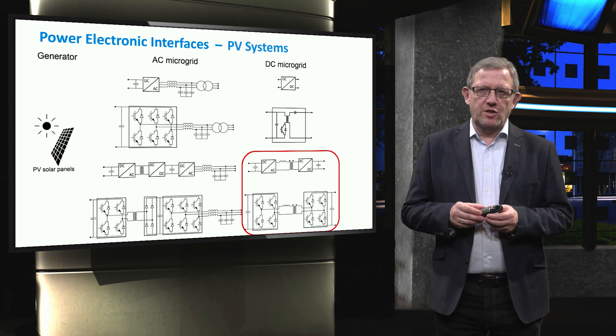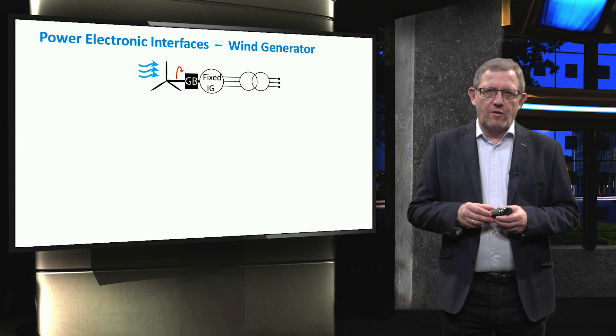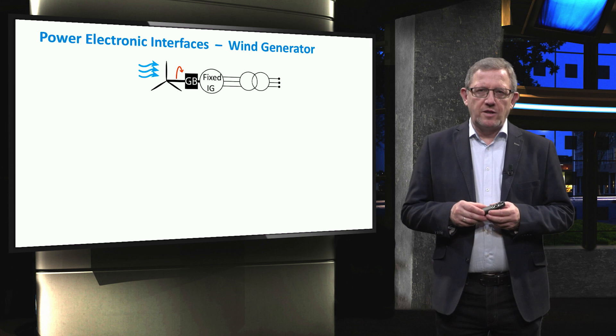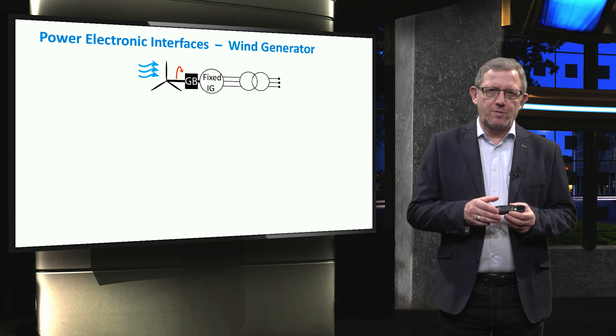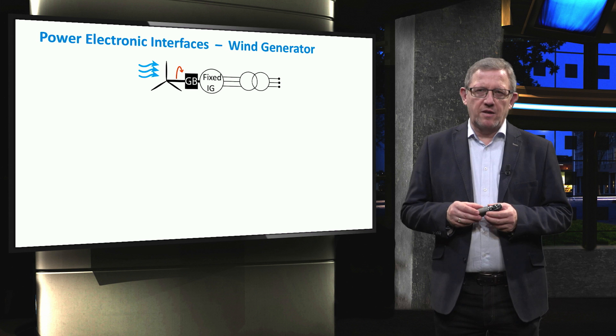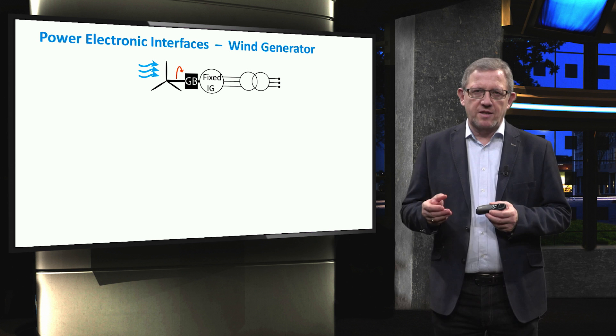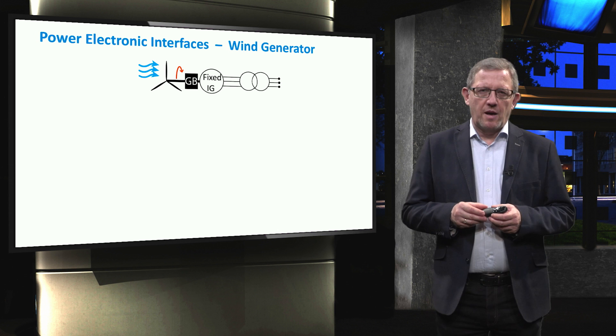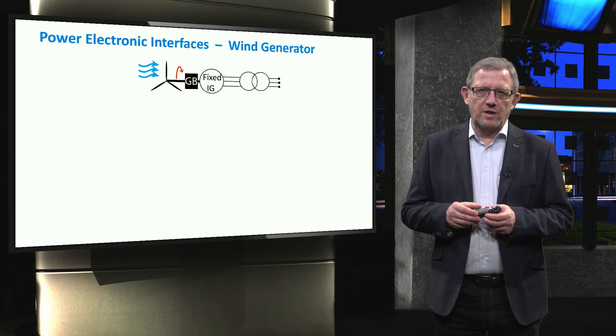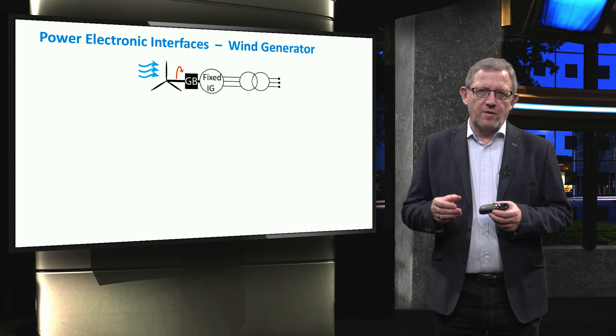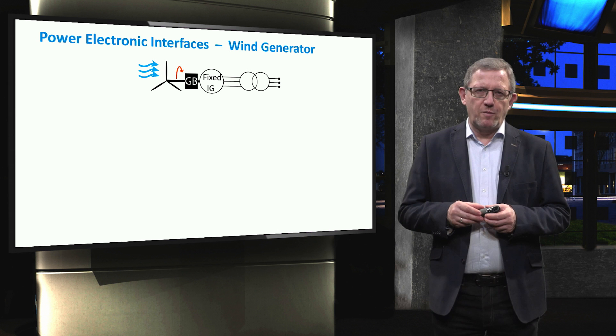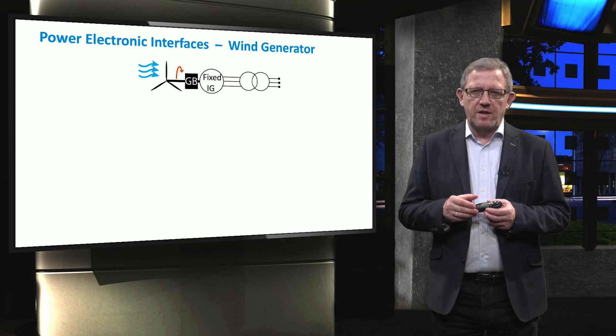The second component for which we introduce its power electronic interfaces will be the wind generator. Wind turbine generators are divided into two generic groups: fixed and variable speed. The fixed-speed wind generators typically consist of a squirrel cage induction machine which injects mechanical power from the wind turbine into the electrical grid. As the rotating speed of the turbine is much lower than the synchronous speed of the induction machine, a gearbox is installed between them, which is expensive and increases power losses. Note that the vast majority of medium-scale wind farms in microgrids are connected to medium voltage levels, so a transformer is used to step up the voltages.